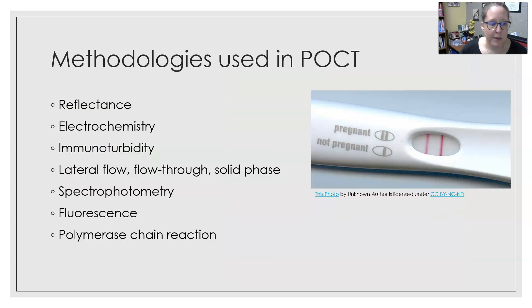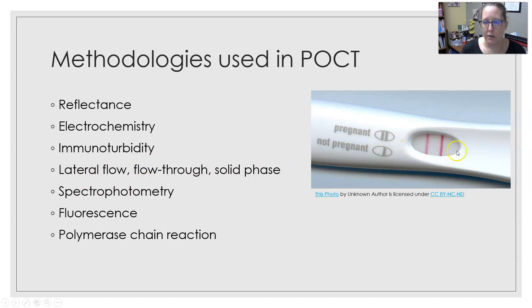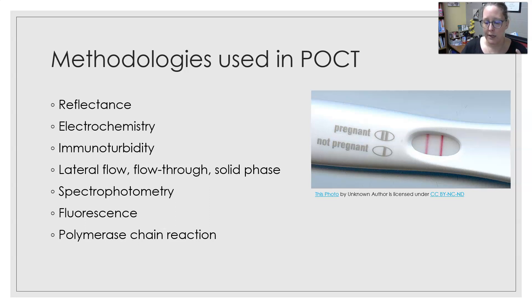The methodologies used in point of care testing include: reflectance, which detects a color change on a surface; electrochemistry, used in ABG analyzers with electrodes to detect gases and electrolytes; immunoturbidity, where antigen-antibody reactions cause turbidity; lateral flow or flow-through solid phase immunoassays, such as the pregnancy test; spectrophotometry, which uses light to detect color changes; fluorescence detection; and polymerase chain reaction, used in many small analyzers doing COVID testing. The next video will cover quality in point of care testing.